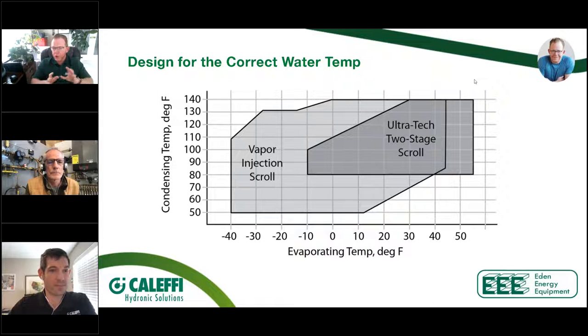One of the things we wanted to show quickly is how a lot of this equipment is able to produce different temperatures, specifically higher temperatures at lower operating temperatures. You can see that on a vapor injected system, here we're talking about that Advantage unit or the IBC unit, even down to minus 40 degrees Fahrenheit, we can still produce 130 degree water. There's a lot of capability here, but back to Max's and Bob's point, if we don't need 130 degree water, if we can creep that back to 100 or 95 degree water, the overall capacity and the overall efficiency of that equipment goes up. Those of you who design your systems around the envelope first are always going to have the most efficient heat pump. And you're going to be the company that has heat pumps running the last 20 years, not 5 years, not 4 years.